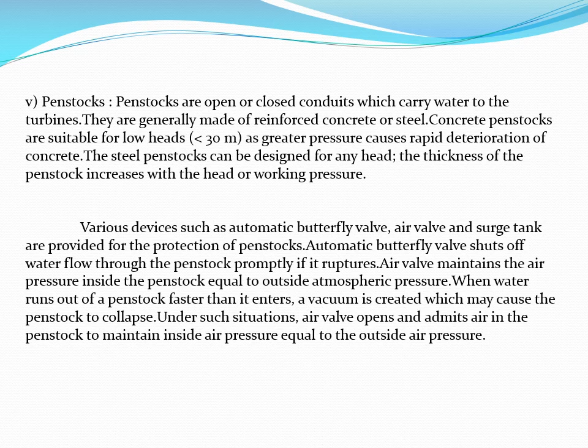The various devices such as automatic butterfly valve, air valve and surge tank are provided for the protection of the penstock. Automatic butterfly valve shuts off water flow through the penstock promptly if it ruptures. Air valve maintains the air pressure inside the penstock equal to the outside atmospheric pressure. When the water runs out of a penstock faster than it enters, a vacuum is created which may cause the penstock to collapse. Under such situations, the air valve opens and admits air in the penstock to maintain inside air pressure equal to the outside air pressure.